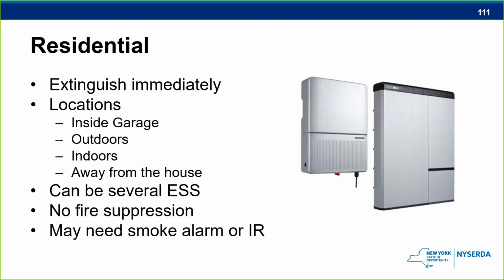So if there was a structure fire and it had nothing to do with the energy storage system itself, the heat from the contents burning inside the building may actually cause a problem with those energy storage systems that are inside the building, on the exterior of the building, or in the garage. Any type of excessive heat that these energy storage systems are exposed to could be a problem. For firefighters, at this particular point, you could probably use your thermal imaging camera and see any rise in temperature, because you can get pretty close to these things. Any type of gases that would be liberated in there that are not on fire should actually exit the enclosure, and the chances of explosion are not great. I can't say it can never happen. Again, that would be irresponsible to say something like that.